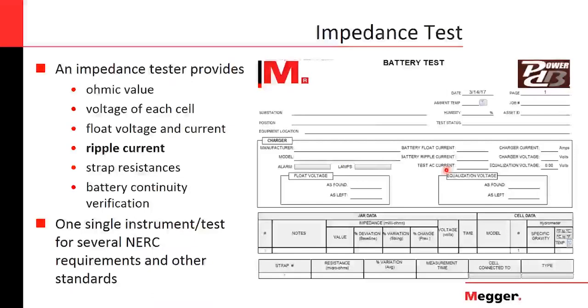And due to the nature of the test and what is being done when you perform it, there's the advantage that you can get other values from this test. So in addition to getting the ohmic value, you get the voltage of each cell, the float voltage also of the entire string. You can get the float current of this entire string. You can get the ripple current, and although this is not one of the requirements from NERC, it's a very important parameter because ripple current can be harmful to your battery.